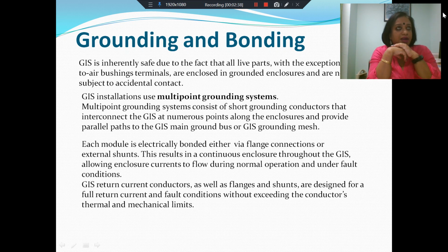And therefore, when you design the GIS return current conductors, you have to remember that currents will be returning through the return conductors, through the flanges and the shunts, and the design should be such that each of these paths taken together are designed for the full return current even under the worst fault conditions without exceeding the conductor's thermal and mechanical limits. So you need to make sure that all these currents can flow through all these multiple paths.